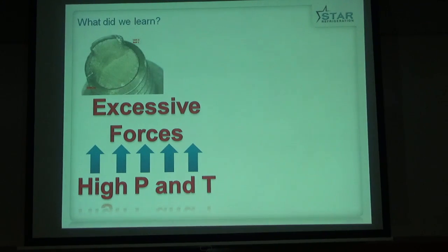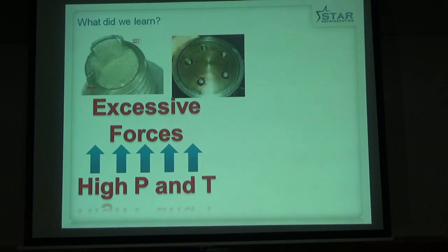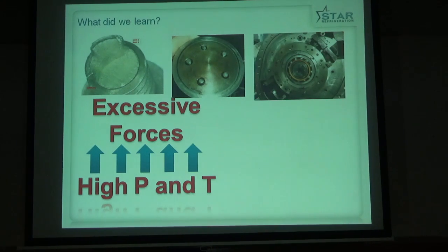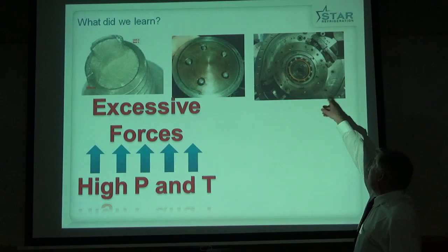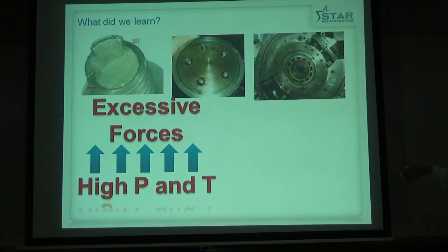We found that because some of the bolts in the compressor had not been really carefully torqued, they'd actually been slightly under-torqued, and therefore they were experiencing a high cyclic force, and we had a fatigue failure of the bolts, which happened to be one of the five bolts that were holding the thrust collar on the end of the shaft of the screw compressor. And when the first one broke, then the second, third, fourth and fifth broke. This is the end of the shaft. You can see the thrust bearing, rolling element bearing there. If you look really carefully, you can see the five ends, the other ends of these five bolts.